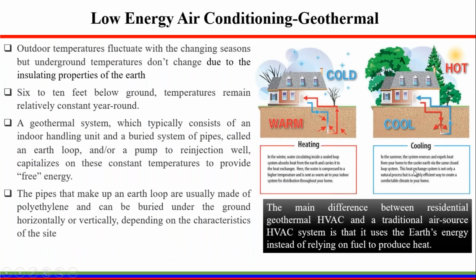Okay. Geothermal based heating and cooling. Outdoor temperature fluctuates with the changing seasons, but the underground temperatures don't change due to the insulating properties of the earth. About 6 to 10 feet below the ground, temperatures remain relatively constant. The geothermal system, which typically consists of the indoor handling unit, the earth loop or a pump to re-injection well, capitalizes on this constant temperature to provide free energy for cooling and heating.